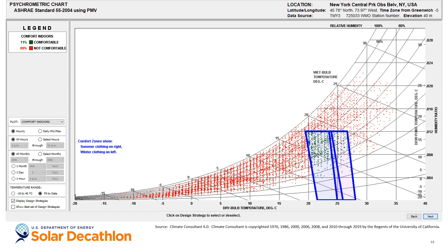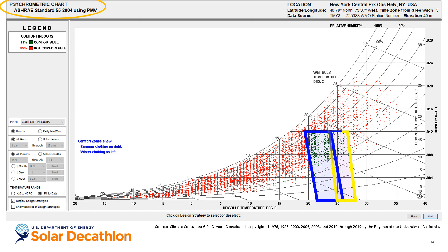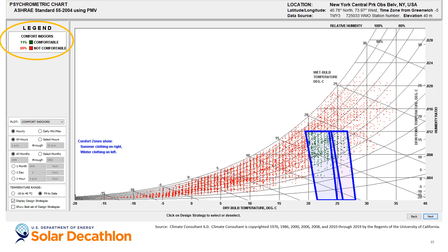The tool also allows us to overlay a box outlining the comfort zone. There are several comfort models developed using rigorous research. The one shown here is based on ASHRAE Standard 55, which accounts for different clothing typically worn in summer and winter. The left box represents the comfort zone in winter clothing, and the right box represents summer clothing. Data points inside these boxes indicate conditions that would generally feel comfortable; points outside feel uncomfortable — too hot, too cold, or too humid. The tool shows that 11% of all hours in a year are within the comfort box, and the other 89% are outside it.